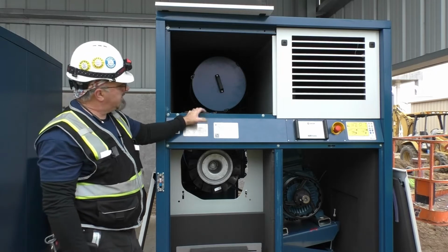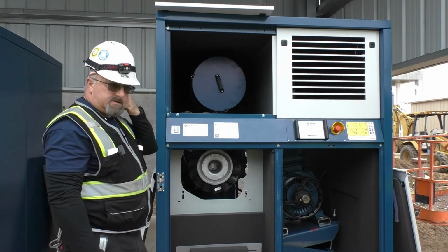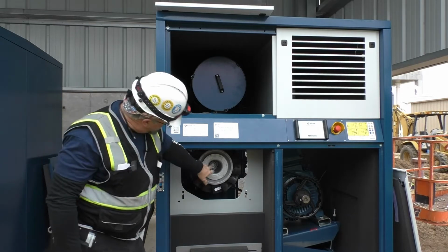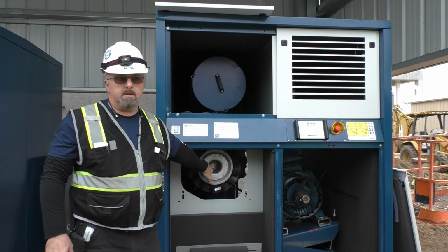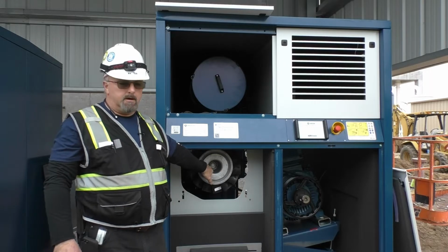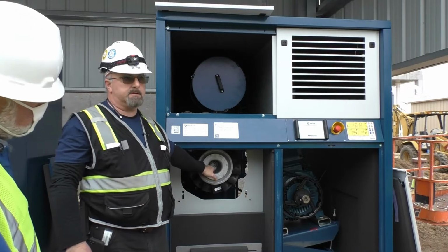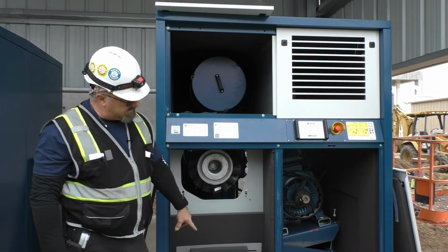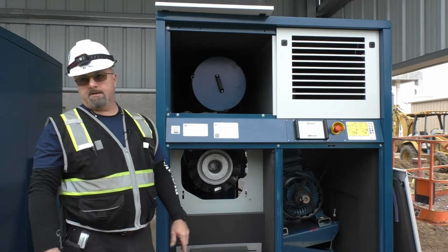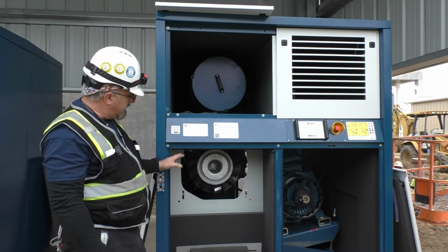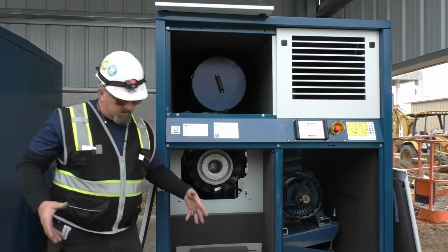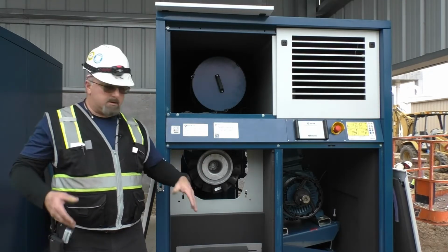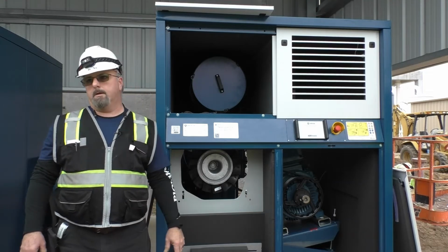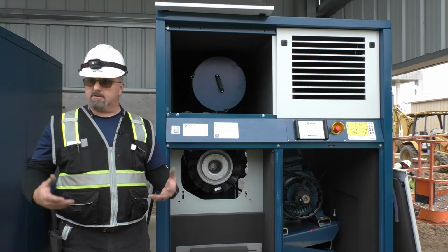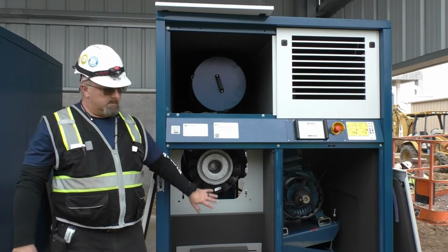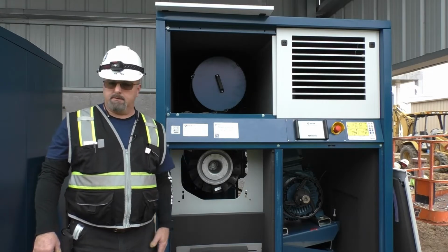Now, when you're doing your inspections of the machine at the 6 month and 1 year point, you're wanting to make sure this bolt inside here is tight. If it gets loose, you're going to know it, because that fan's going to start wobbling. It's going to hit that fan guard, and it's going to start making a lot of noise. Now, if this cover here was to shift and come in contact with the fan, you will be able to identify that as well, because it sounds like a scrubbing noise. So if you hear that, you want to make sure your fan clearance is good.